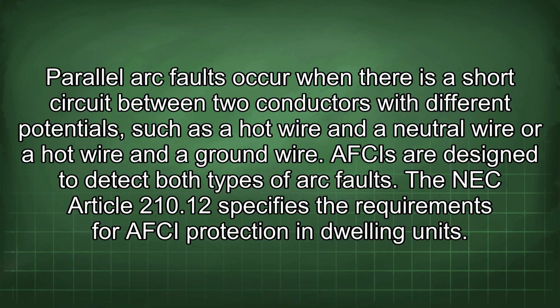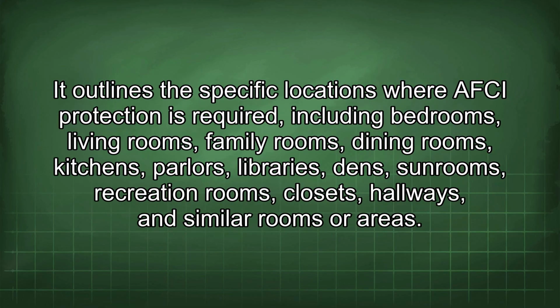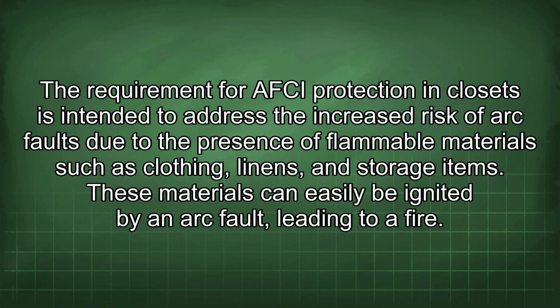NEC Article 210.12 specifies the requirements for AFCI protection in dwelling units. It outlines the specific locations where AFCI protection is required, including bedrooms, living rooms, family rooms, dining rooms, kitchens, parlors, libraries, dens, sunrooms, recreation rooms, closets, hallways, and similar rooms or areas. The requirement for AFCI protection in closets is intended to address the increased risk of arc faults due to the presence of flammable materials such as clothing, linens, and storage items. These materials can easily be ignited by an arc fault, leading to a fire.